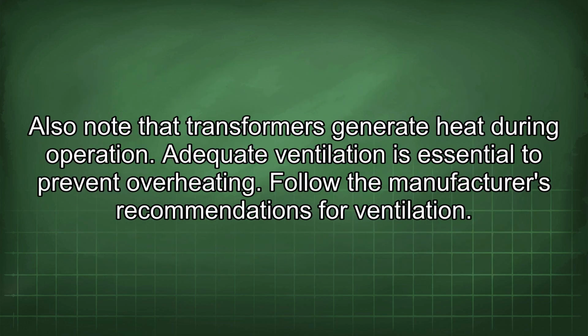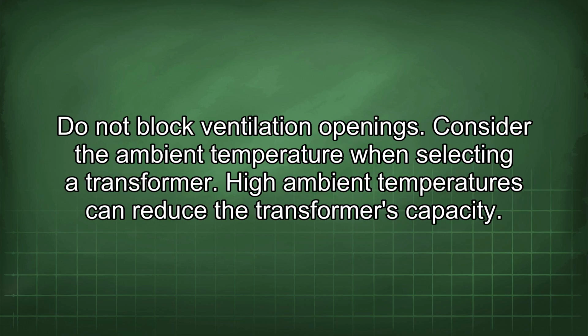Also note that transformers generate heat during operation. Adequate ventilation is essential to prevent overheating. Follow the manufacturer's recommendations for ventilation. Do not block ventilation openings. Consider the ambient temperature when selecting a transformer. High ambient temperatures can reduce the transformer's capacity.